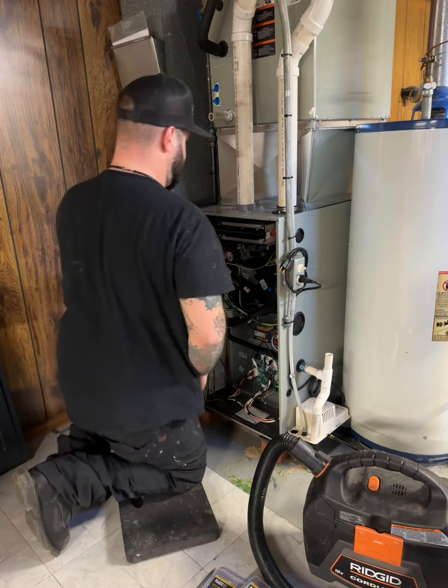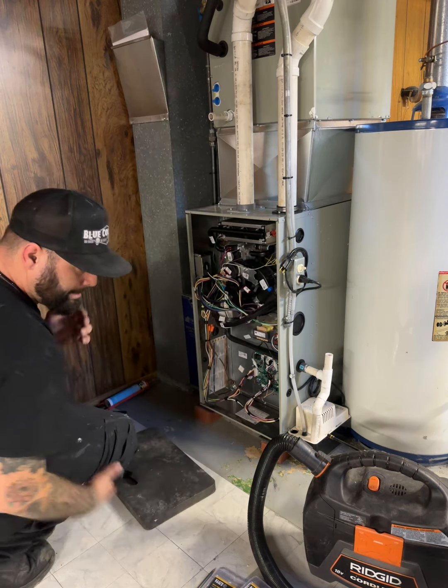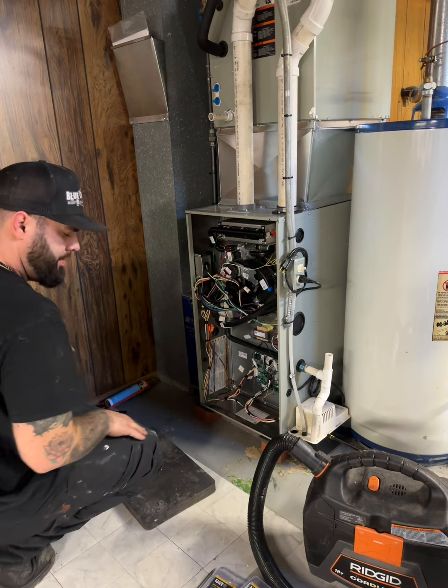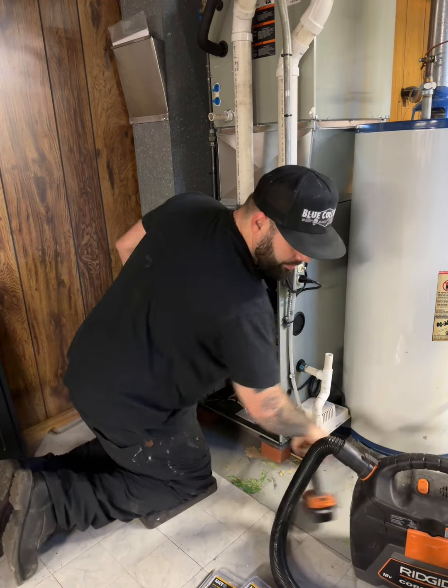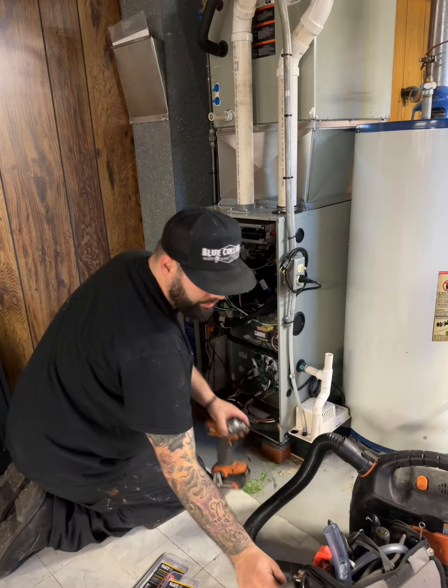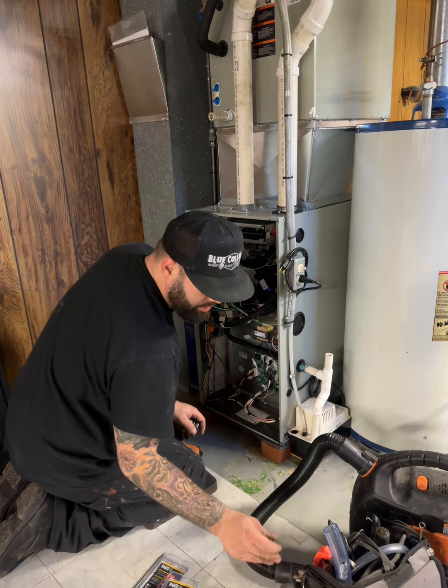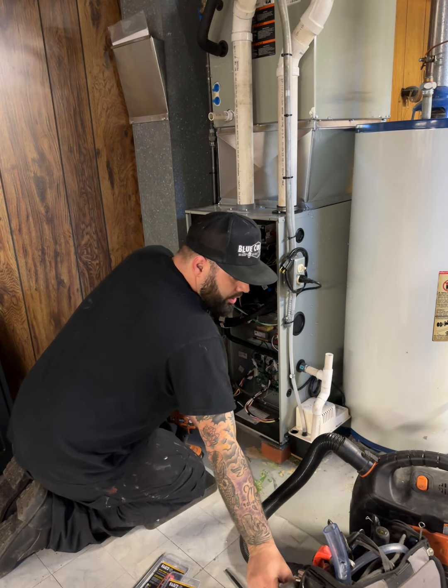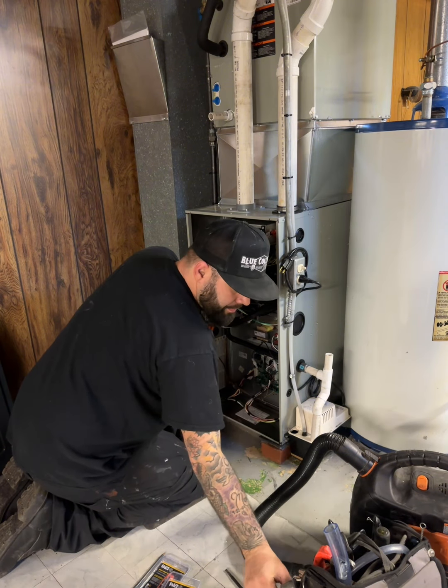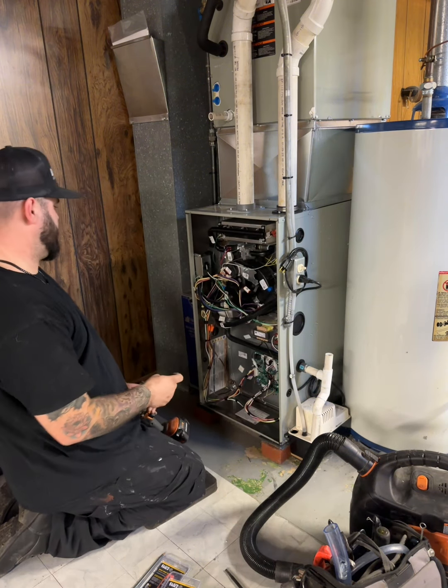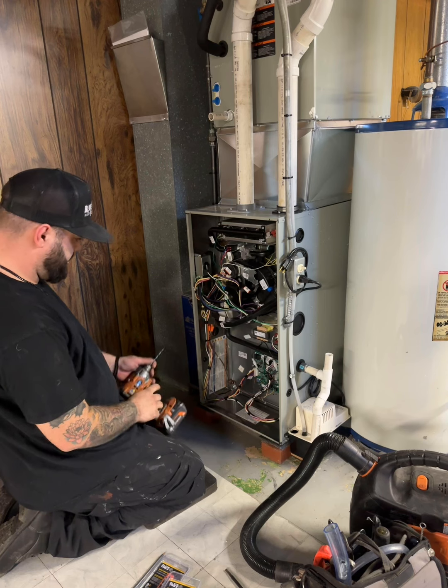Alright, so here we go. We got our knee pad, we're going to do our checks. We got our manometer in our bag. We'll check gas pressure, we'll check static pressure, and verify the unit is in good shape.